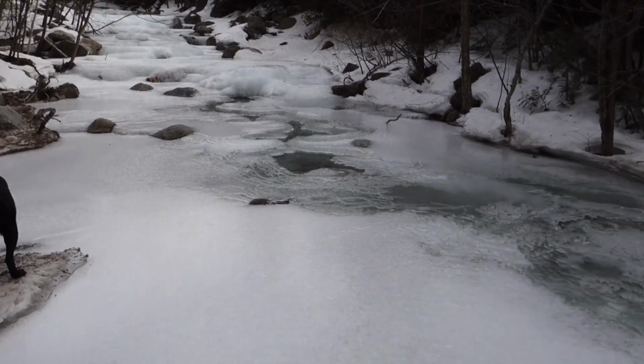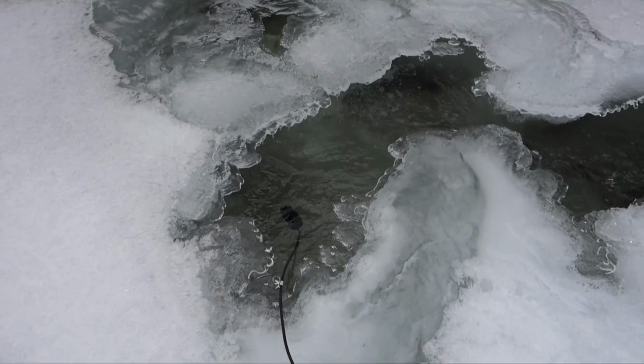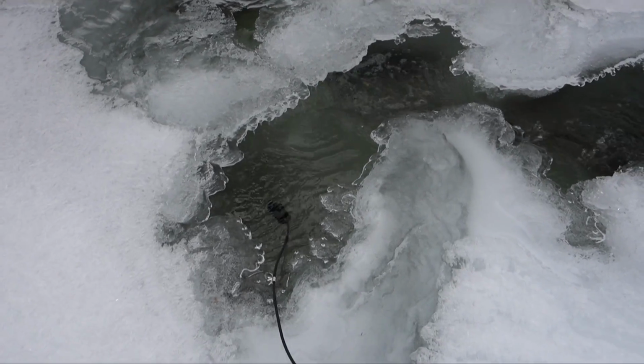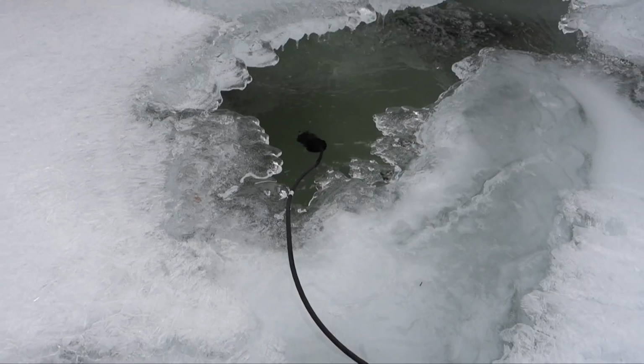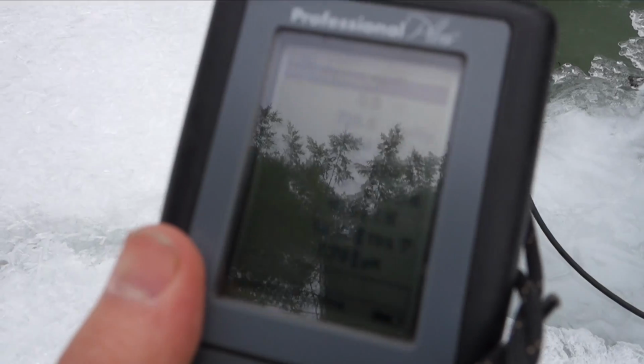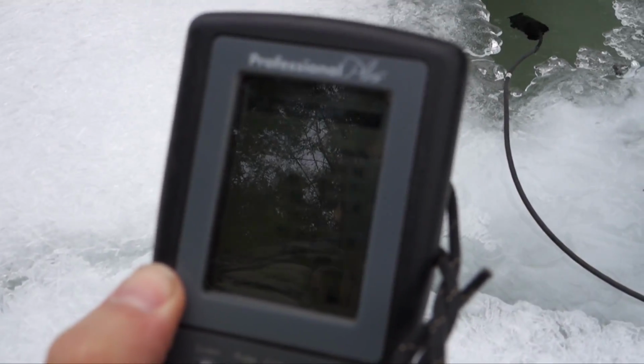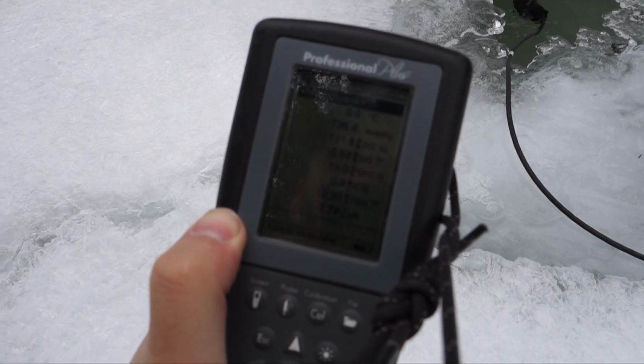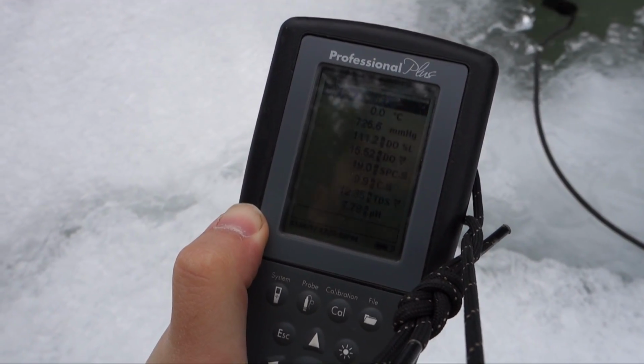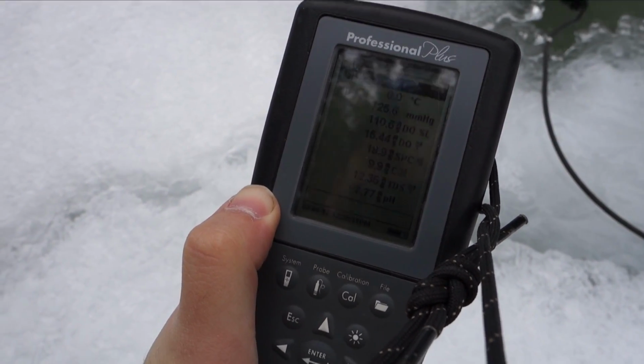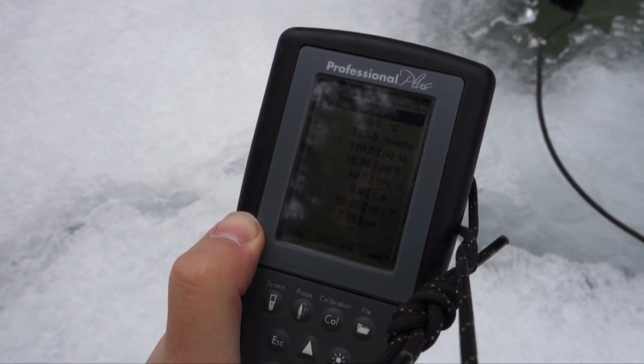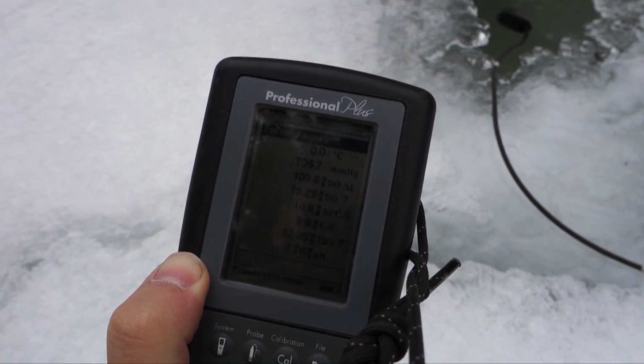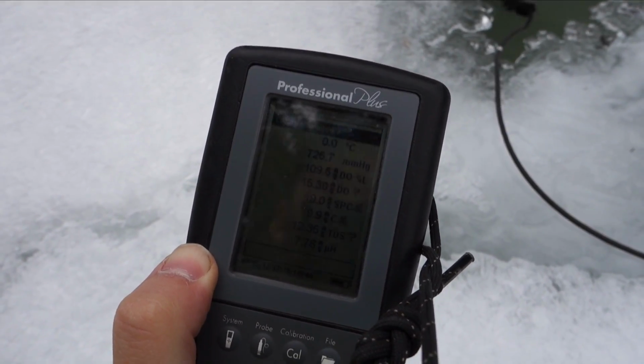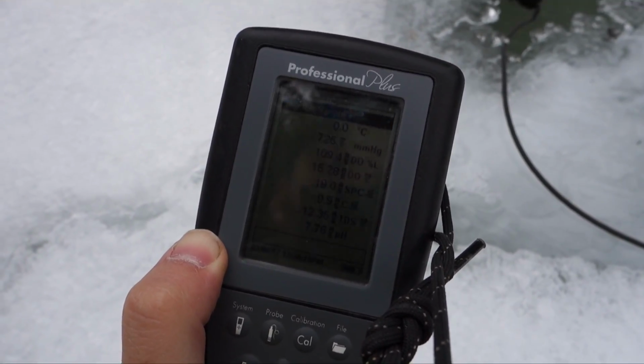So it's mostly frozen over right now, but we do have a little bit of open water for us to get our sonde into and take a reading. So if we look at a screen of our multi-parameter probe, conductivity is 19 microsiemens per centimeter. So much lower than Norton Brook and within the range we would expect for a stream that is not impacted by road salt.